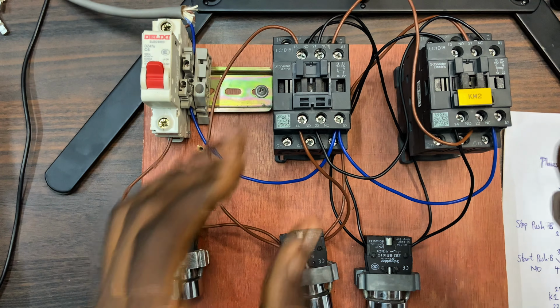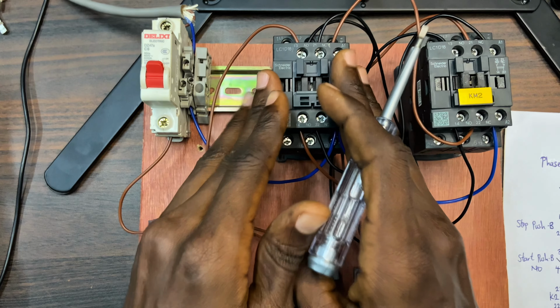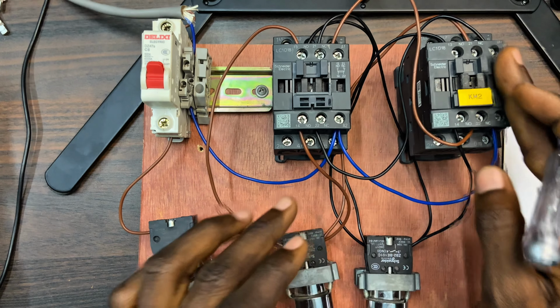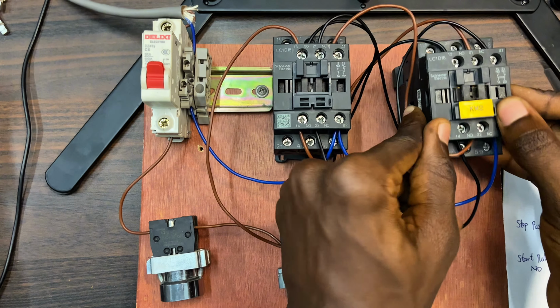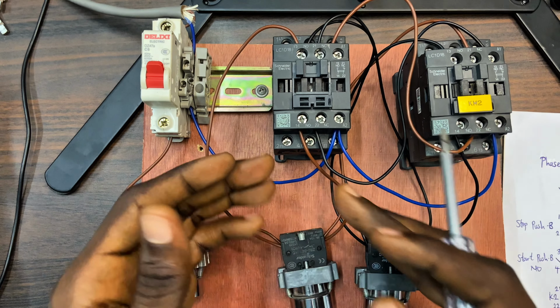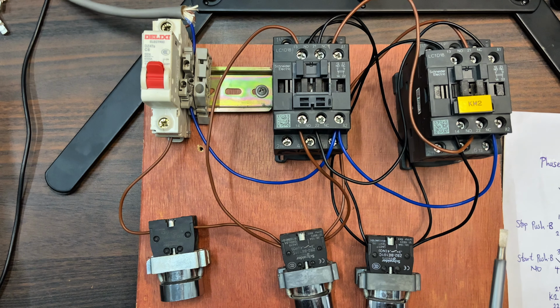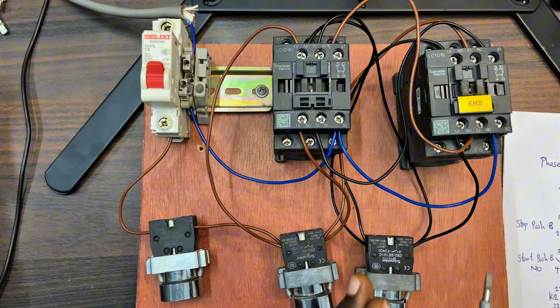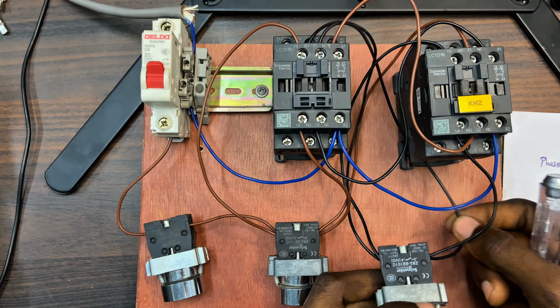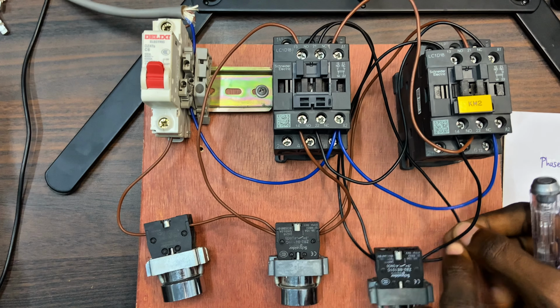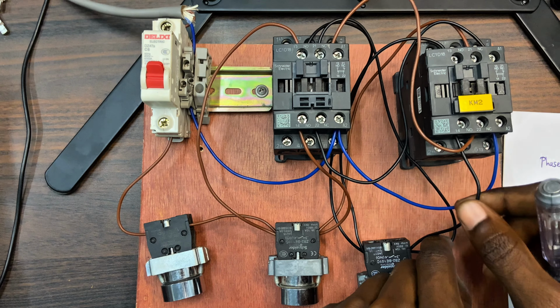Now, one contactor is serving as the forward contactor and the other as the reverse. When this contactor is also able to energize, there's going to be a short circuit in the power cables to the motor. That's why we are doing the interlocking. And the reason why this push button is not working is that we have the switch wire. This is the switch wire. This is the hold on. The 14 and the 13 is the hold on, this cable.